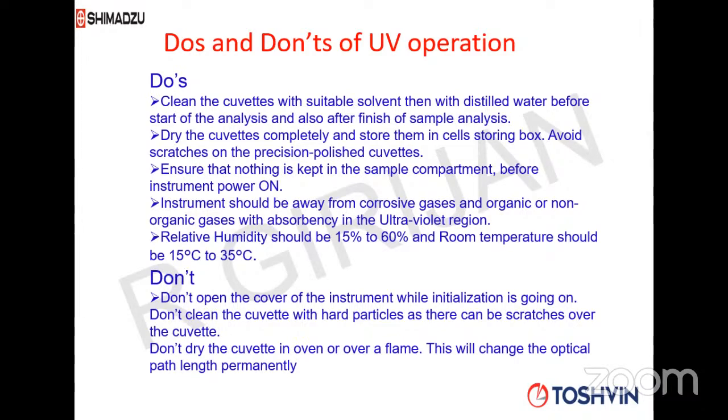You should never dry the cuvette in the oven. Even though glass and quartz are basically non-conducting materials, when you keep them inside a heated oven, minute thermal expansion can take place, which will alter the path length. That will affect your quantitative result.